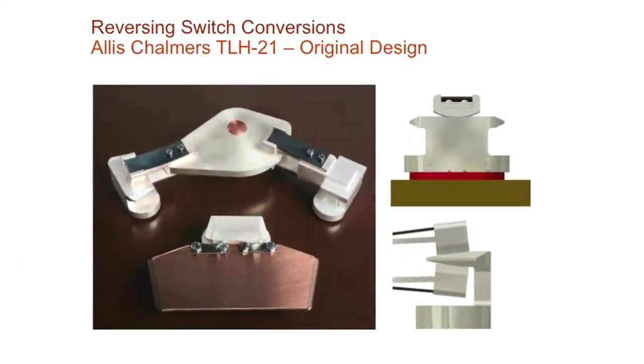We've created this new switch, which basically has 3 fingers on top, 3 fingers on bottom, and then they ride on this rail when they start reversing. They go from here to here. And what that allows it to do is with the 6 fingers, it cleans the contact surface. So it's not building up that film as frequently as it would with the one flat, solid piece of copper. So it's actually doing what we call a wiping of the contact when it goes on and a wiping when it leaves. So you reduce the contact wear a little bit. You also reduce the coking effect that goes on in these LTCs.